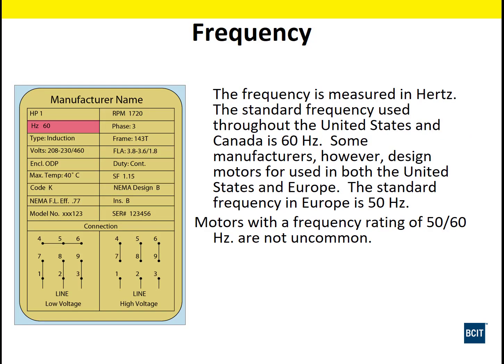Next thing we look at is frequency. It's the design frequency at which these motors were intended to operate. European and Asian motors quite often run off of 50 hertz. It's getting pretty common to see combination 50, 60 hertz motors. They might have different voltage ratings at that time.